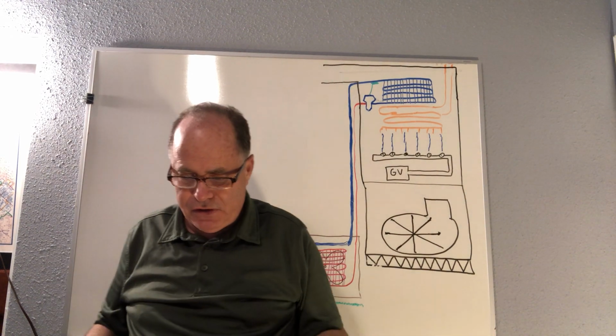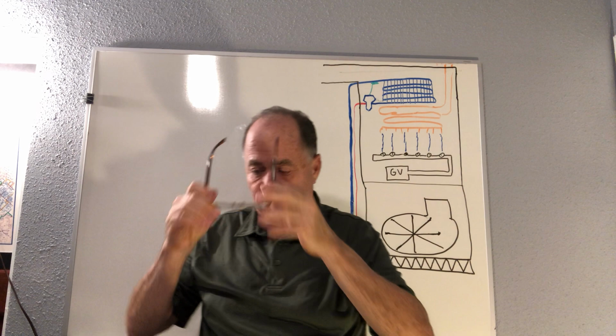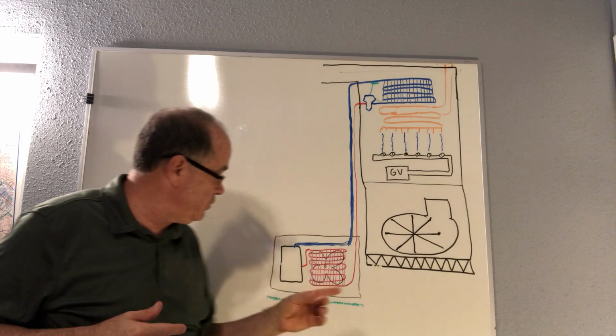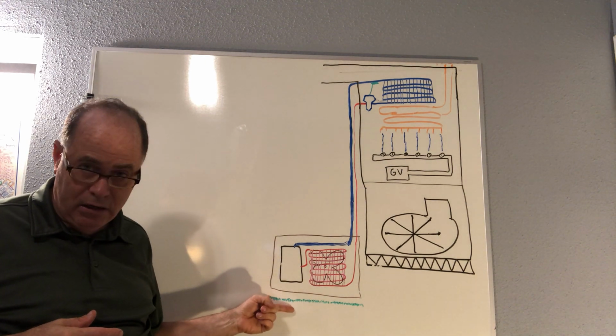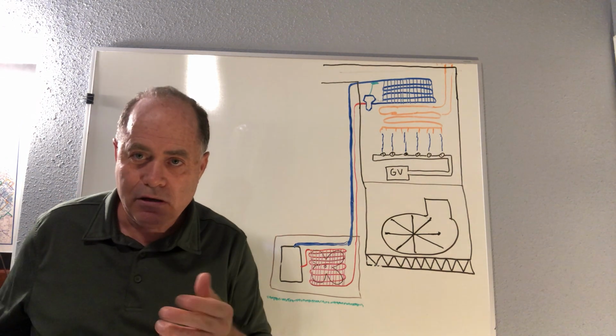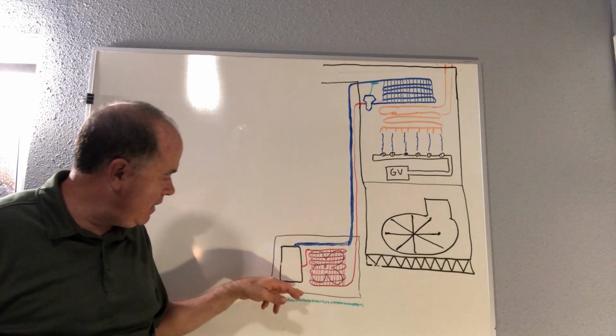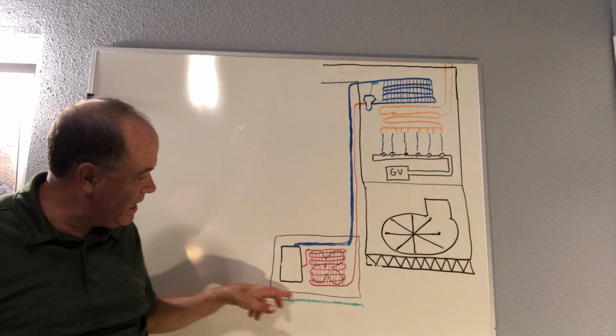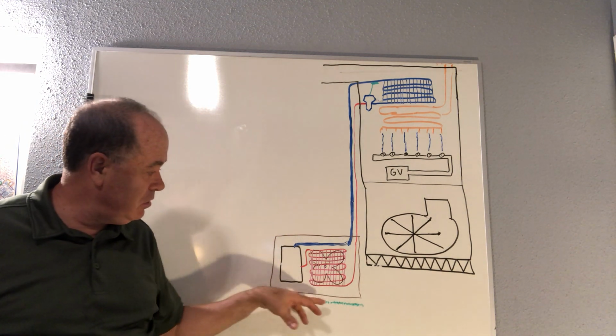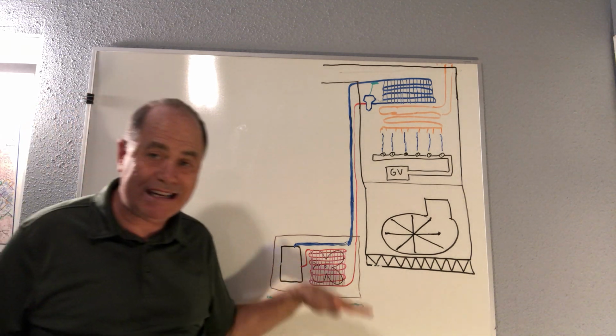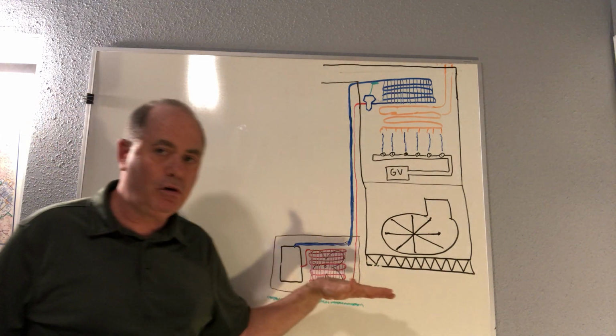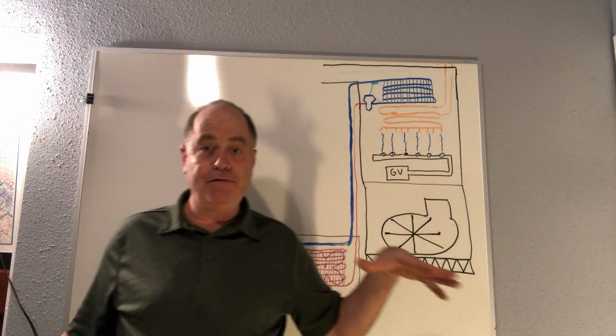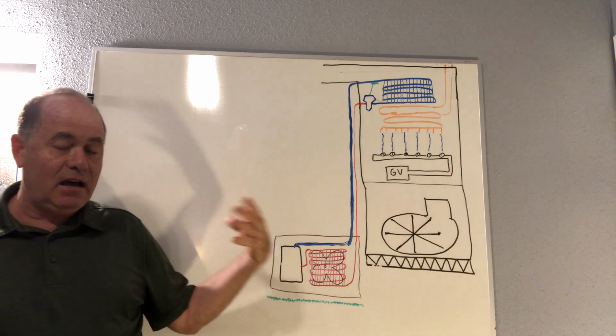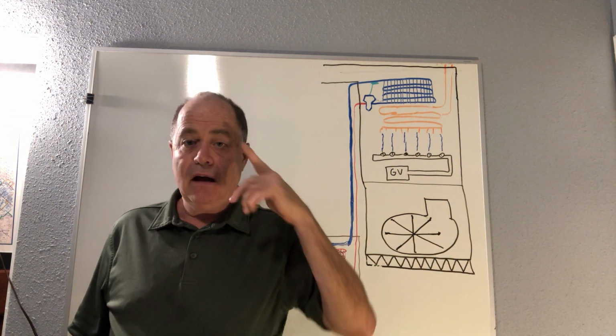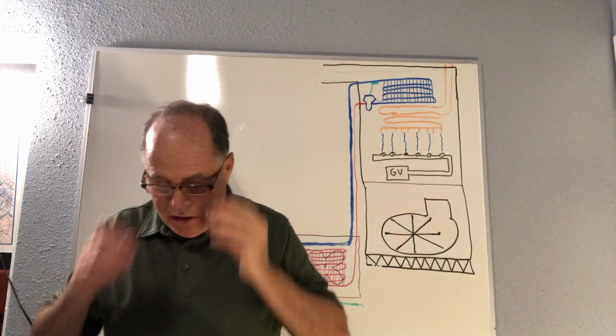Then evaporative coolers, the slang name is swamp coolers. They have to be 3 inches up off the ground. Even that's a rule also for condensing units. You see the little green here? That's grass. I took the time to draw you a little grass. And the white is a cement pad or a pad from the manufacturer or parts house, 3 inches to keep the condensing unit and the evaporative cooler off the ground, so that if there's a flood, or a heavy rain, water won't get inside your unit, okay?